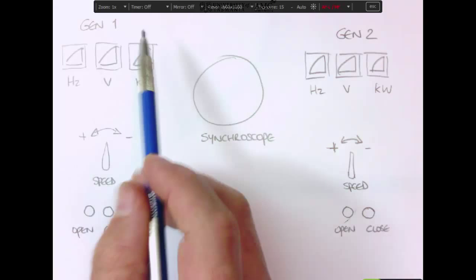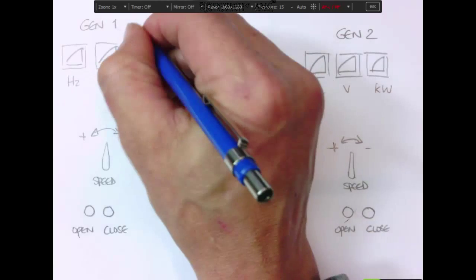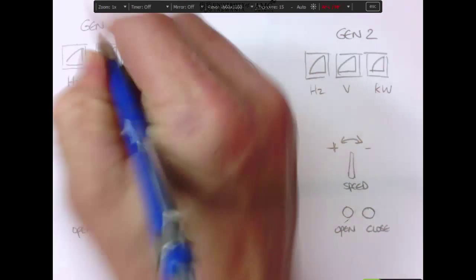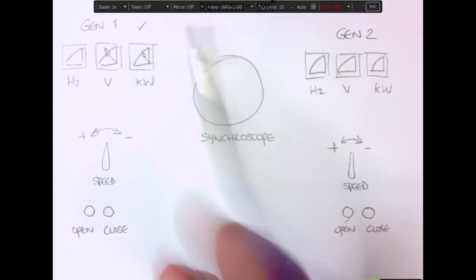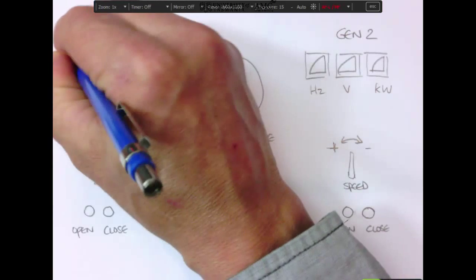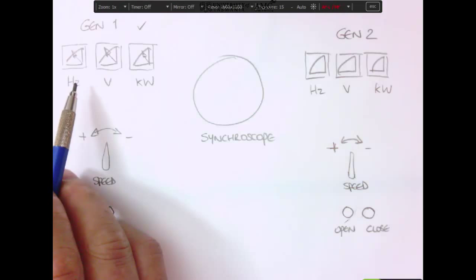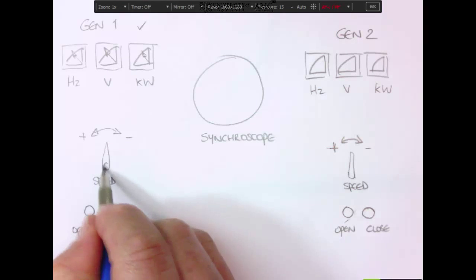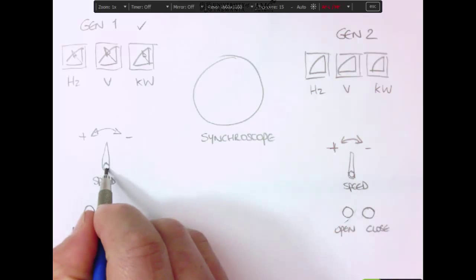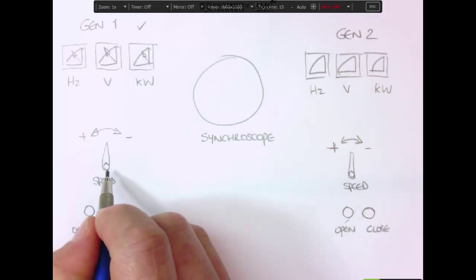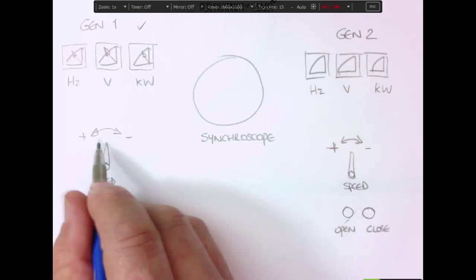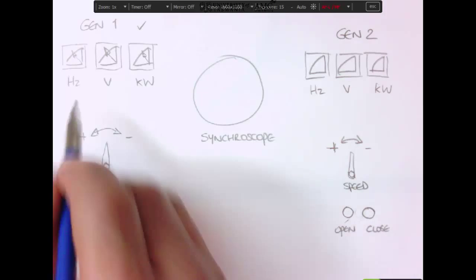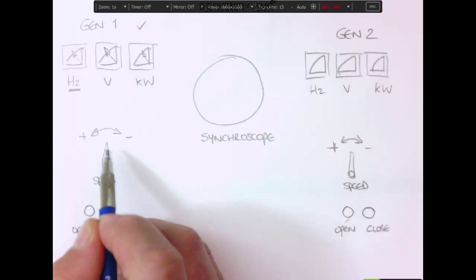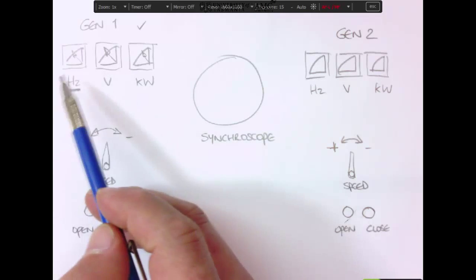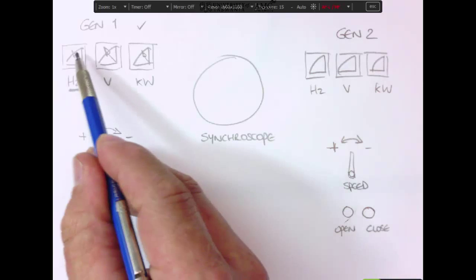So at the moment, let's assume that generator 1 is running. We call that the onboard machine. And so it's going to be showing 415 volts. It's going to have some sort of kilowatts on it. Let's say 220 kilowatts. Our frequency is going to be sitting on 50 Hertz. Okay, and here we've got two speed controls. So in the manual setting, I can adjust the speed of my generator, which affects the frequency either by raising or lowering it. If I raise it, it's going to increase the frequency. If I lower it, it's going to lower the frequency.